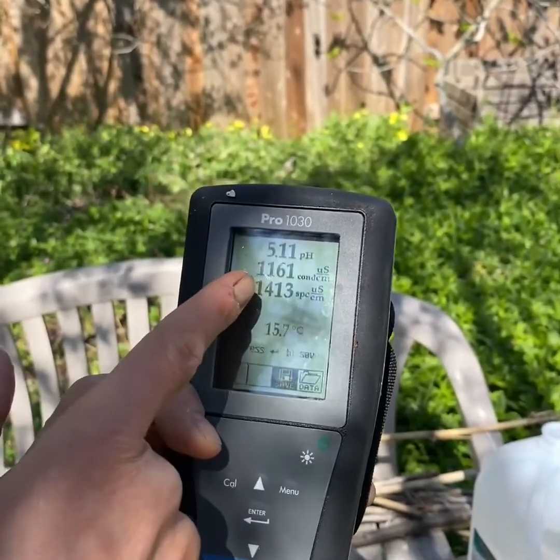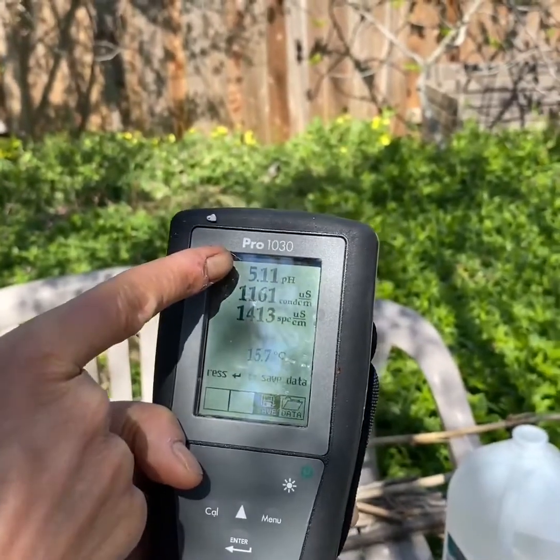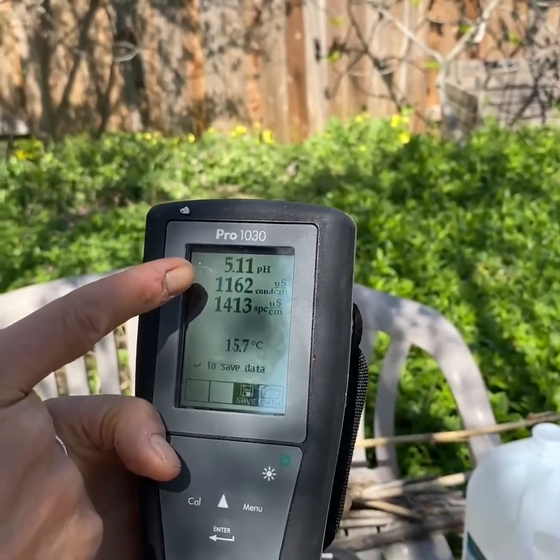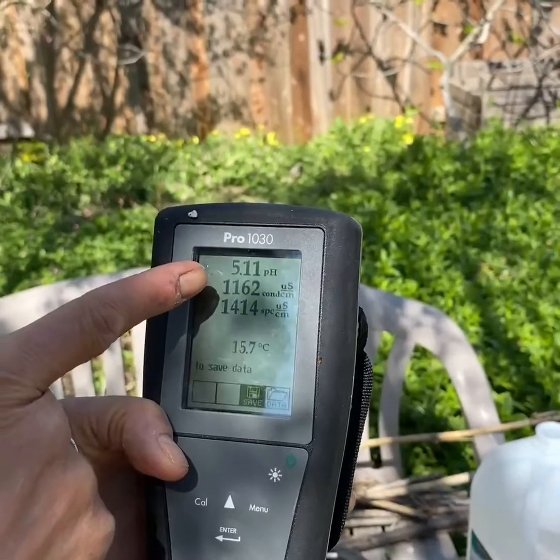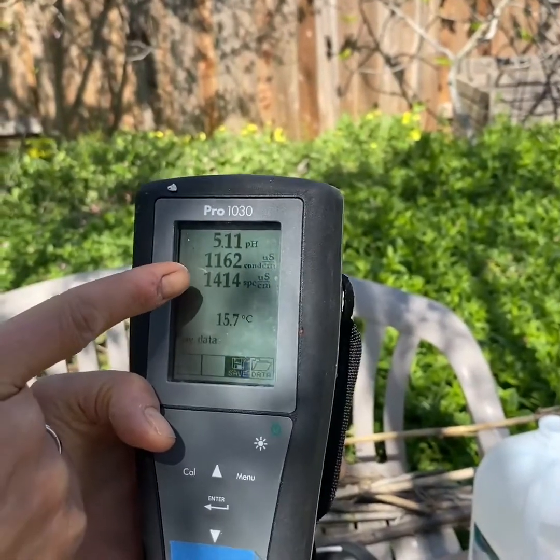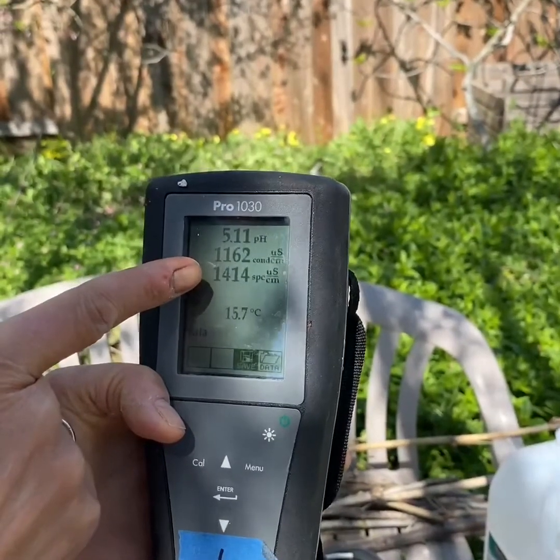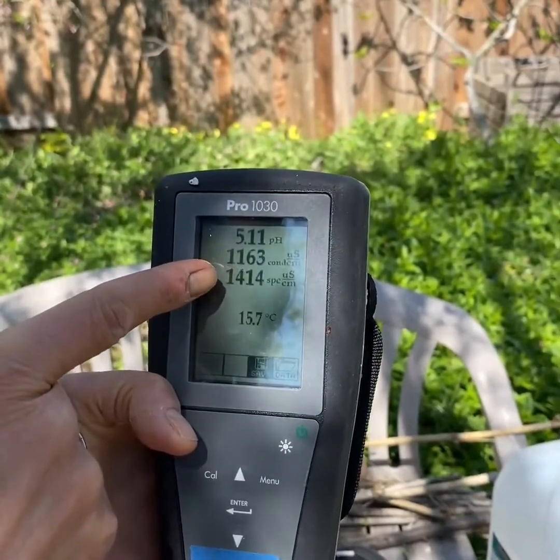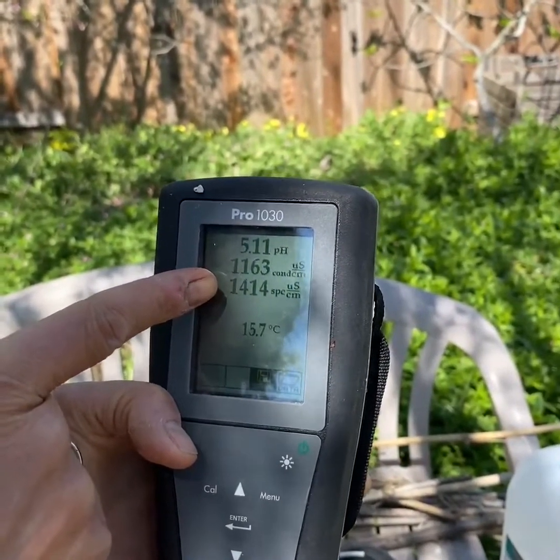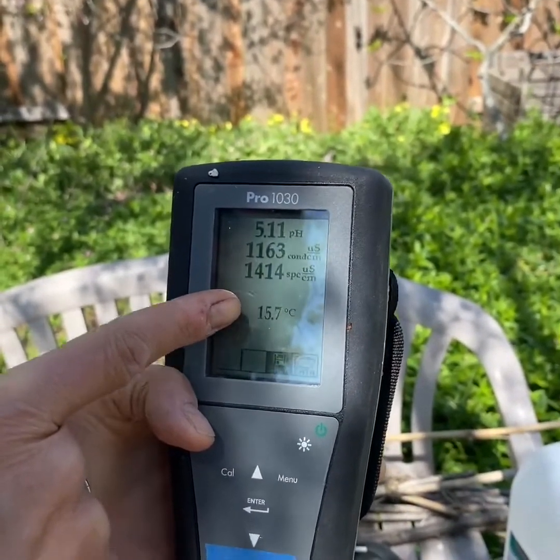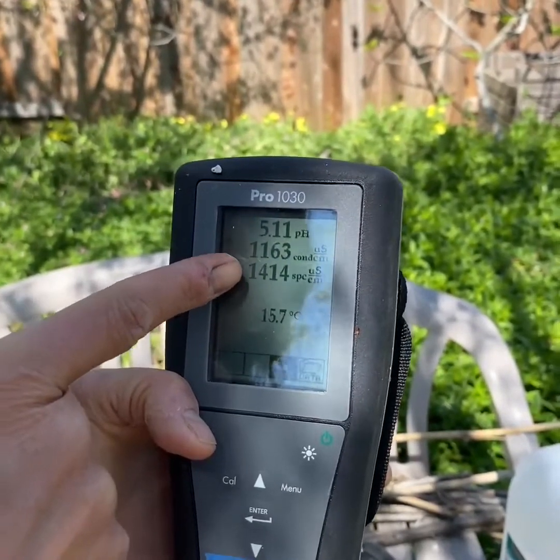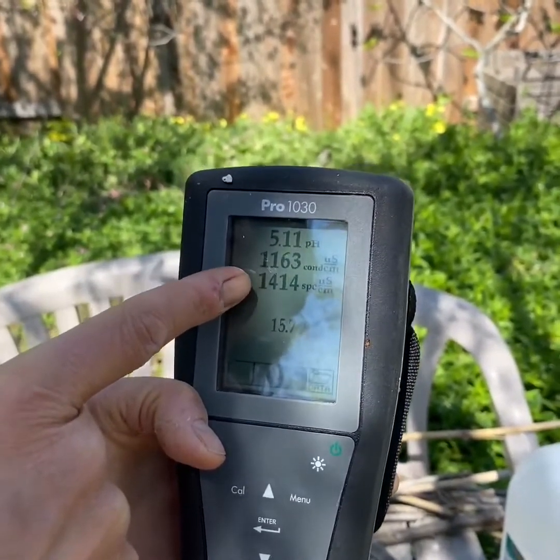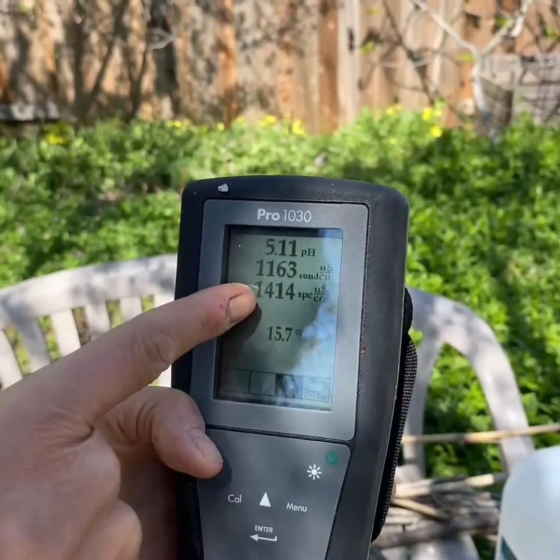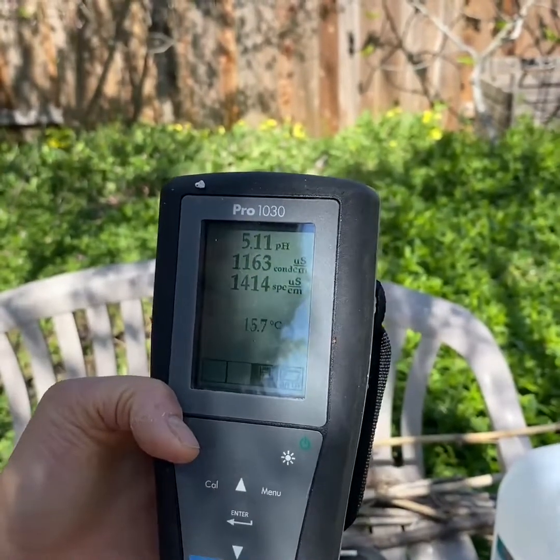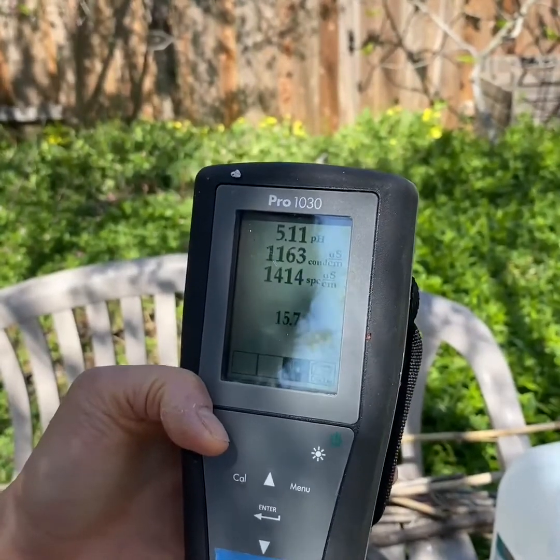And when we go back to the reading, it gives us the pH on top, the conductance in microsiemens per centimeter, and then specific conductance. And that's the one we want, the one that's corrected for 25 degrees Celsius. Oh, see, look, it's actually only 15.7 degrees here. So we'll read this one, the 1414. It's 1 unit off, which is still well within error range.